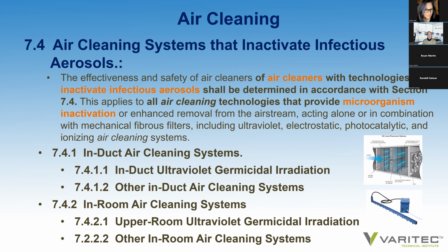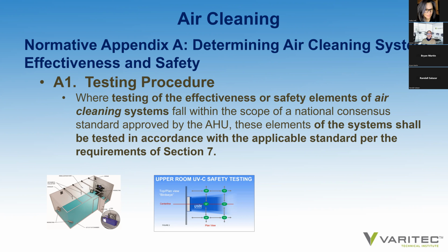What is interesting is that ASHRAE's previous language on ionization was that it is an emerging technology that needs to be given further study. Well, now that technology is being looked at, providing it meets the air cleaning effectiveness ratings as prescribed by a third-party testing agency to demonstrate its air cleaning capability. Section 7.4 also addresses in-duct air cleaning systems, in-duct ultraviolet germicidal irradiation and other air cleaning solutions, as well as in-room cleaning systems such as upper room ultraviolet light and perhaps other directly delivered solutions into that space to reduce concentrations of pathogens.